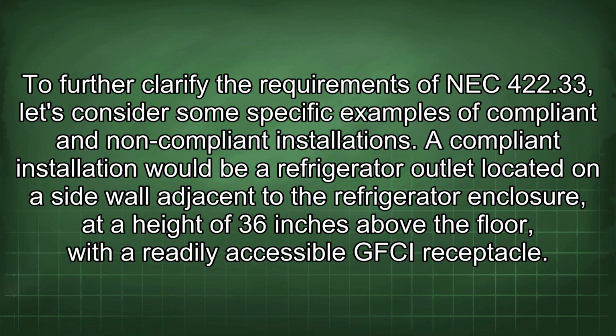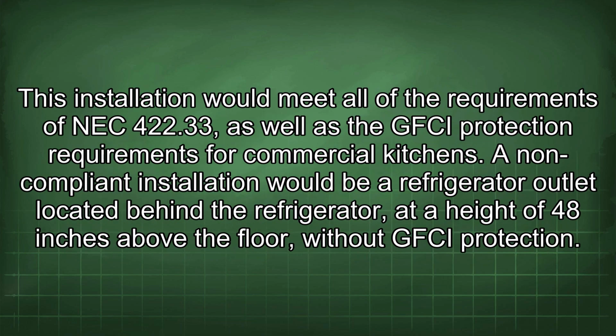To further clarify the requirements of NEC 422.33, let's consider some specific examples of compliant and non-compliant installations. A compliant installation would be a refrigerator outlet located on the side wall adjacent to the refrigerator enclosure at a height of 36 inches above the floor with a readily accessible GFCI receptacle. This installation would meet all of the requirements of NEC 422.33 as well as the GFCI protection requirements for commercial kitchens.